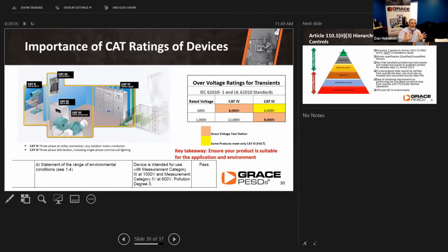Real quick, just know that these devices are going to be used throughout your facility. It could be at an individual tool like a drill press, at 120 volts or 208 volts. Could go into your distribution panels. It could go to your variable frequency drives, your motor feeds, fan feeds, and also all the way up into your incoming utility equipment, onto some of the MCCs and other locations. And the device is intended for use with measurement all the way up to Cat 3 1000 volt rating and Cat 4 at 600 volts.